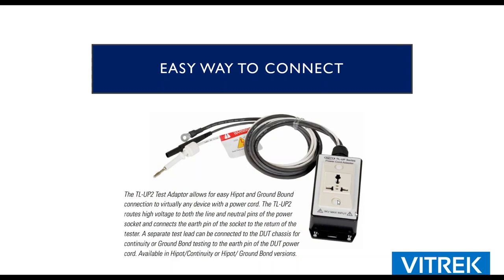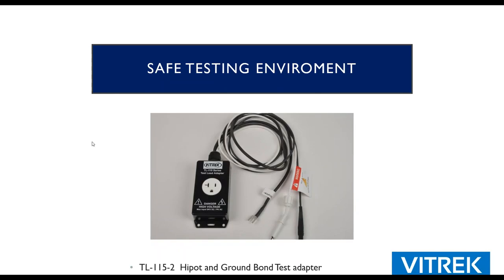If you use something like this, the TLUP adapter, it allows you to make half of a ground bond measurement and an entire Hipot measurement. Your power cord plugs in there, you take another alligator test lead and you clip that onto the chassis of your device, and you've made a safe, reliable connection that's also going to be consistent. And you're able to use a variety of international power cords with this box. If you choose not to use international power cords, this is the way to go. If all of your products are the NEMA 5-15 connector, go with this option. It obviously works better to use a designated outlet for your power cord than one that is more flexible and versatile. So there you go.